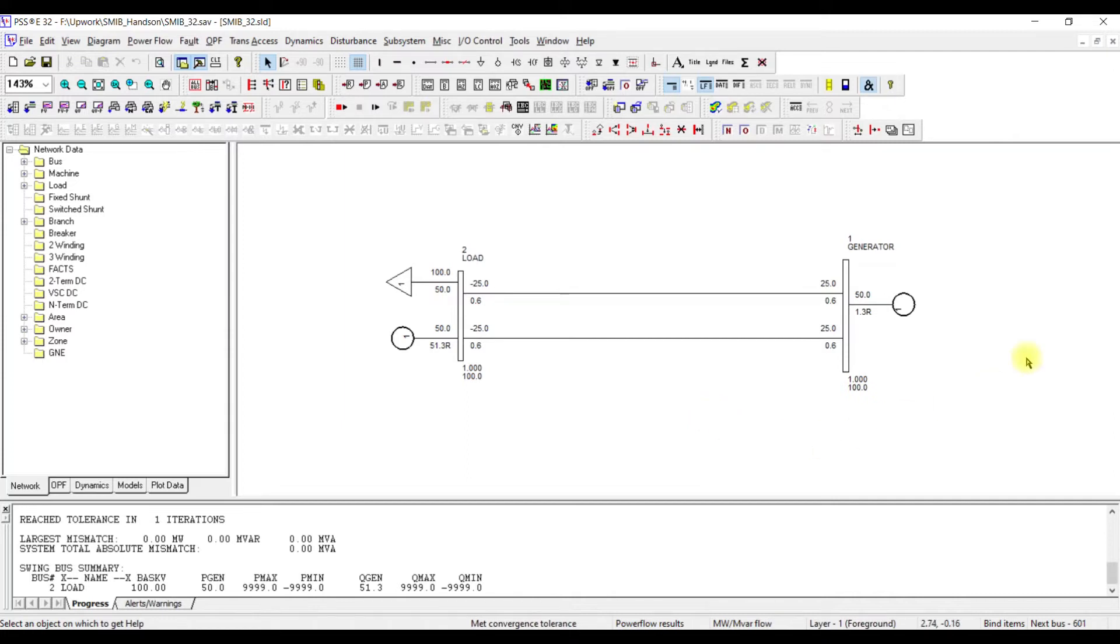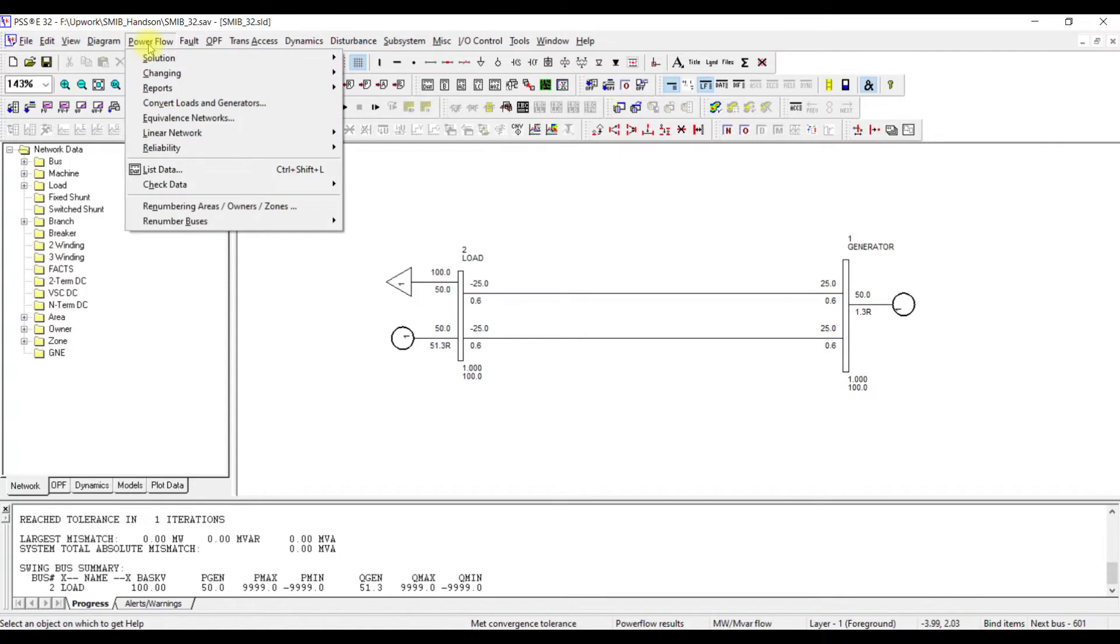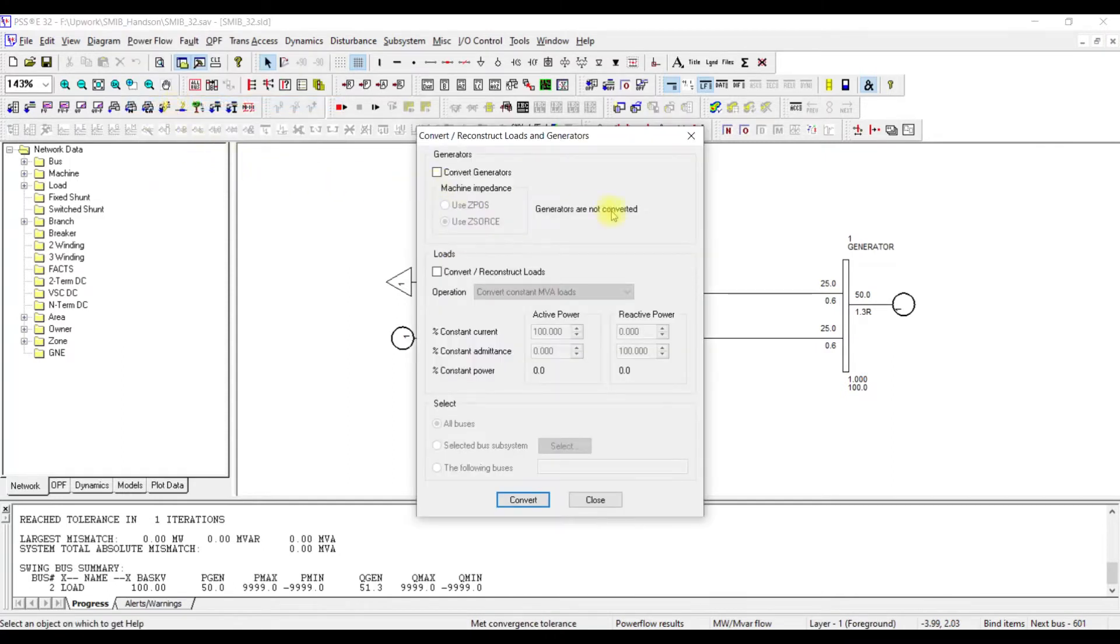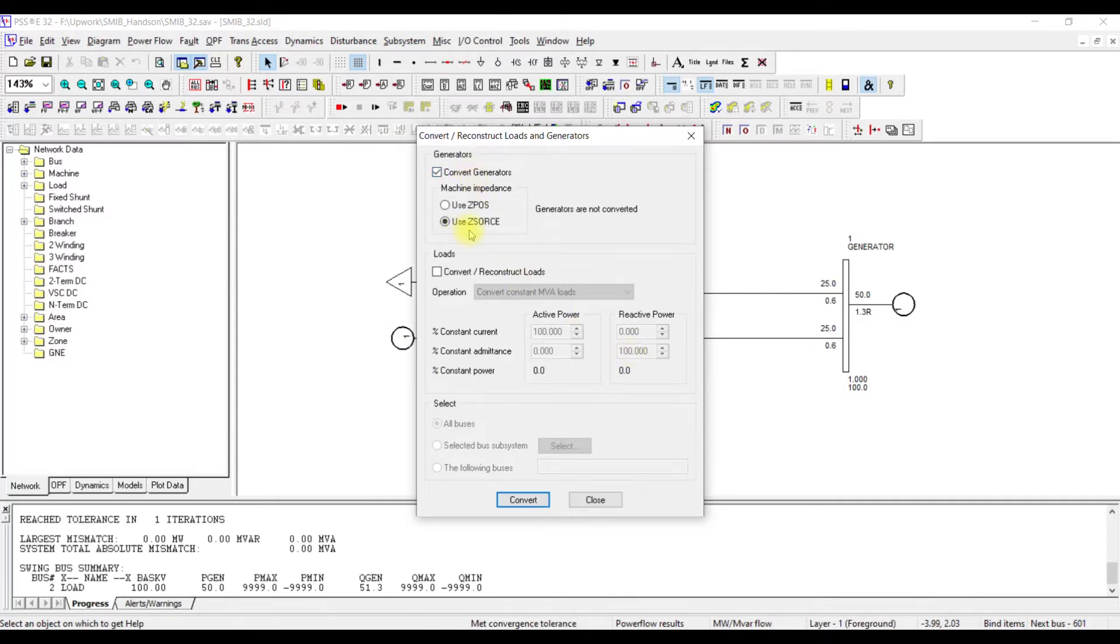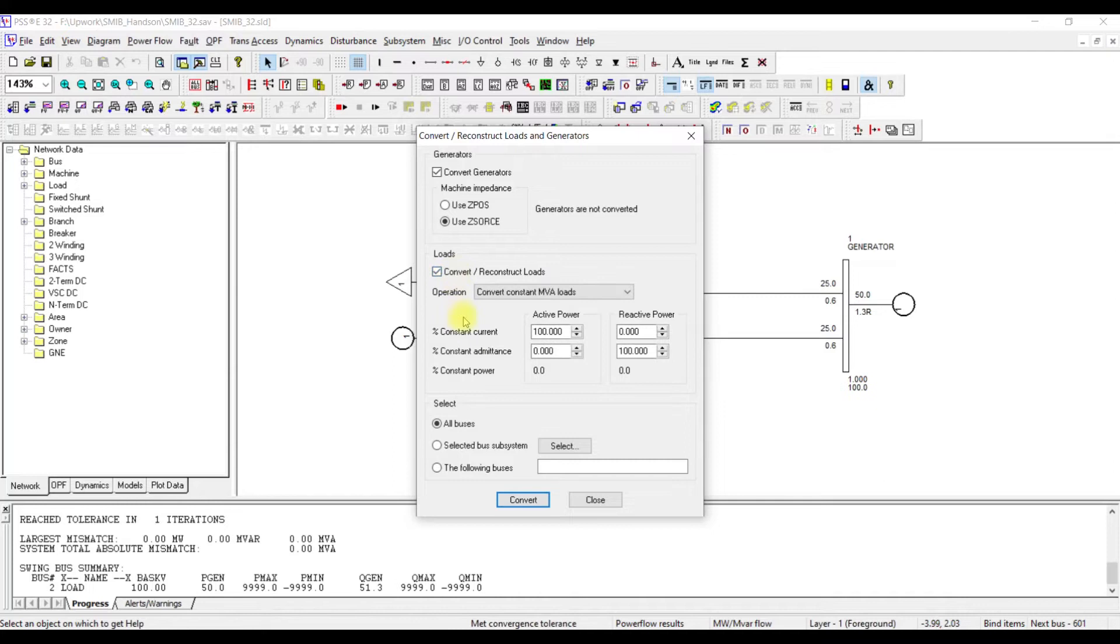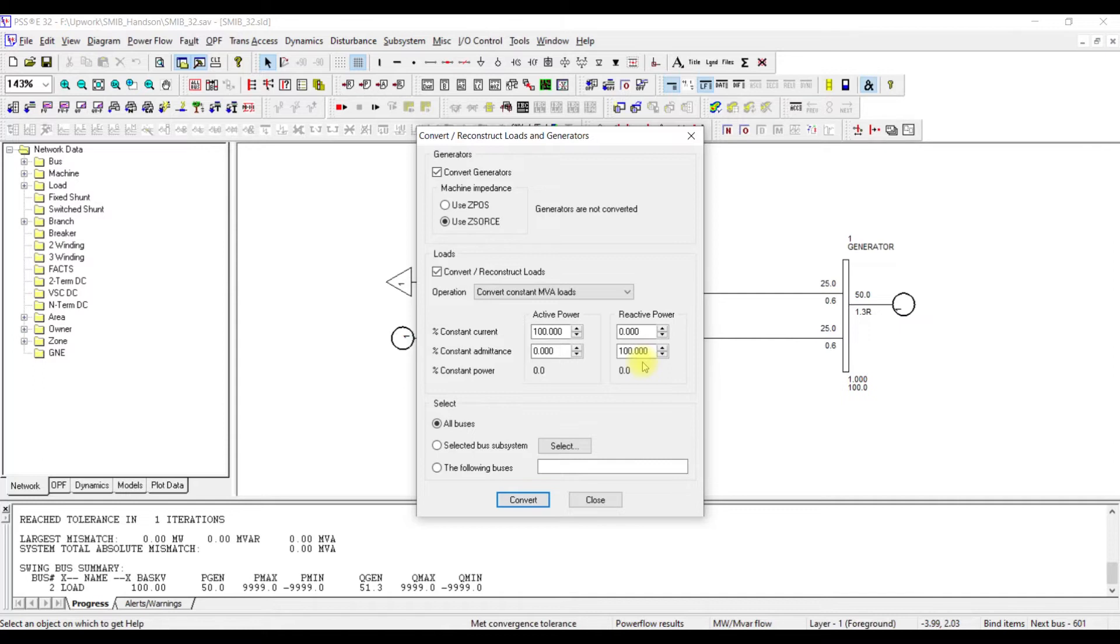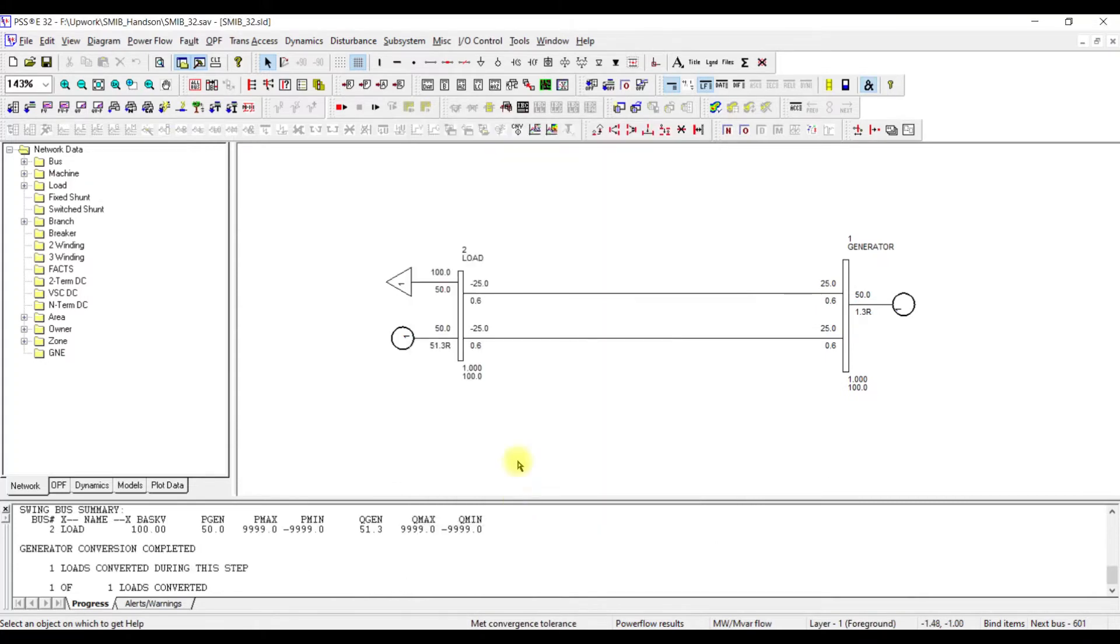Now, we need to convert this case into its Norton equivalent or current injection source. How can we do that? To perform this analysis, we have to perform some tasks. The first task will be to go to power flow, go to convert load and generators. When you click on the convert or reconstruct load and generator, a window is going to open. In this window, select convert generator and use Z source. Use Z source as the conversion. Similarly, we need to reconstruct the loads. For reconstructing the load, we are going to take the worst case scenario which is my active load is going to be 100% constant current load and my reactive power load is going to be 100% constant impedance load. This will provide us with the worst case scenario for the load. Always use this option. We want to perform this option for all the buses in the system, so keep it all buses and press convert. This way, my system has been converted.